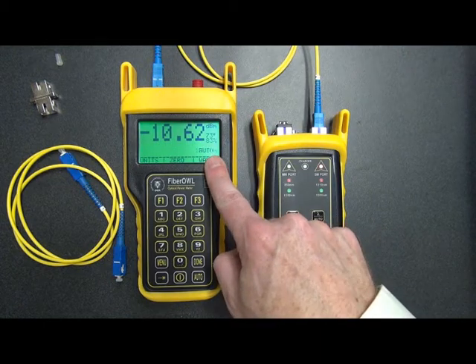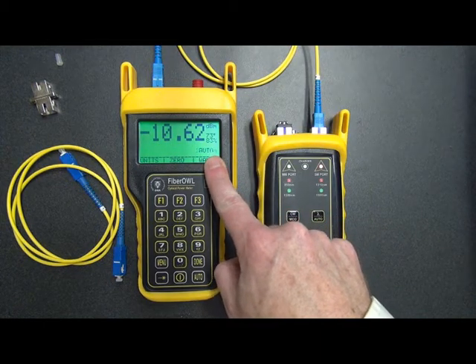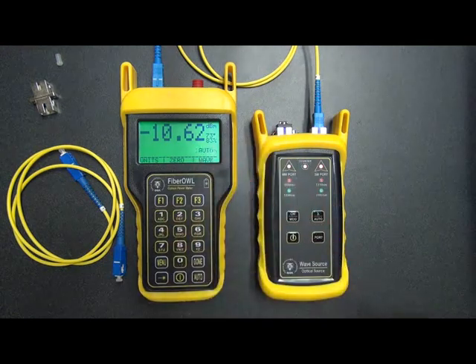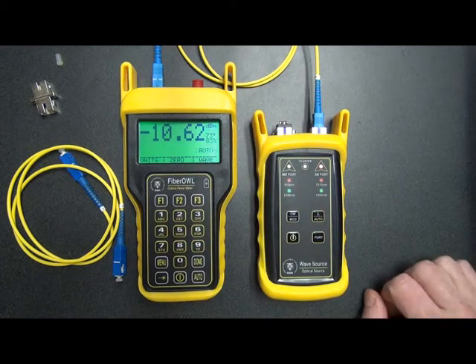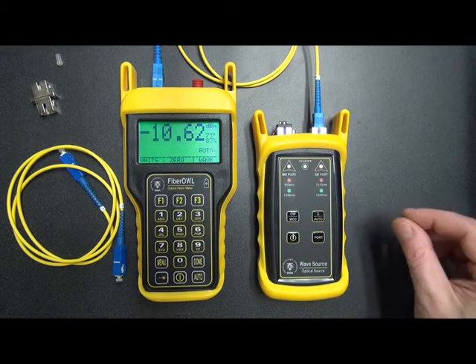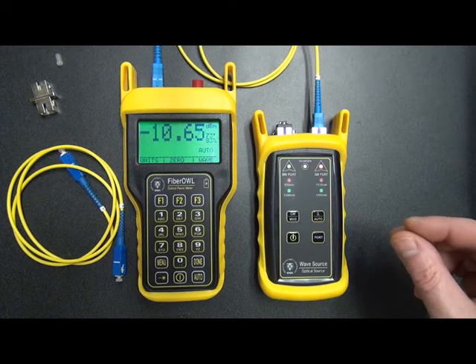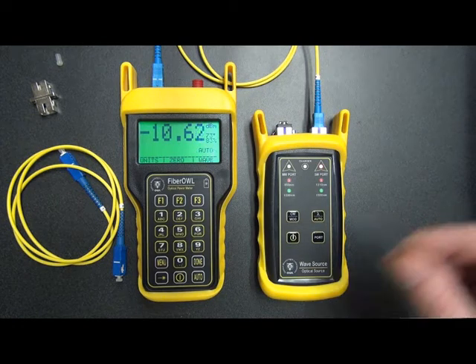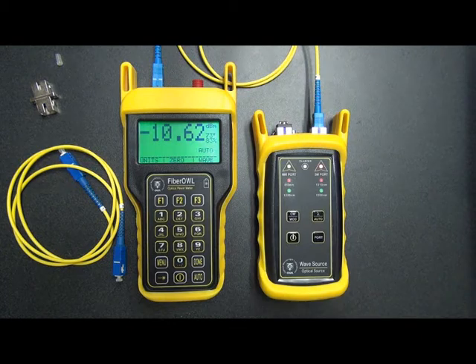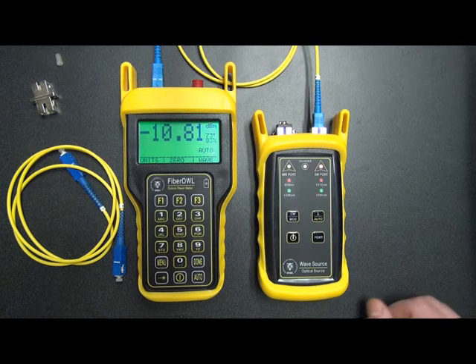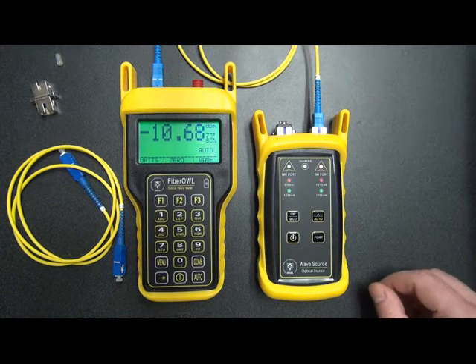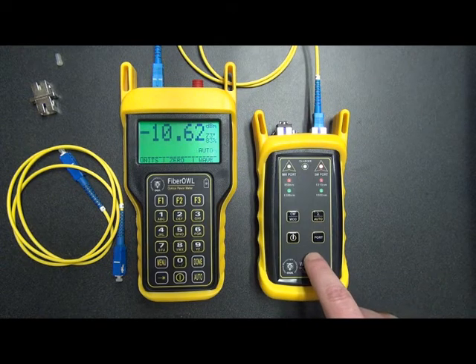The wavelength indicator will now say 1310 auto, and it will be switching back and forth between those two words. What this means is that the FiberOWL is receiving light, but it's not receiving an auto testing signal. It's just scanning incoming signals for auto, which it's not getting at this point. So we need to set the WaveSource into auto mode as well.